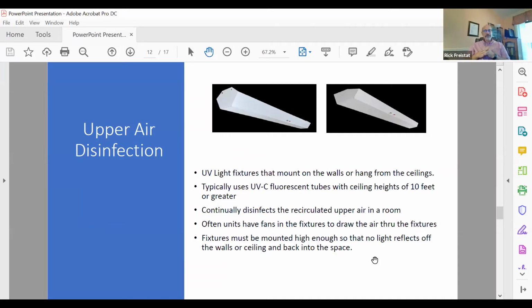The good news about UVC is it disables viruses; the bad news is you can't take too much of it. It's a very strong energy and irradiation that can hurt your eyes or skin. So whenever UVC is being used to kill viruses, you can't be in the room, and fixtures need to be mounted high to ensure light doesn't come down into the room. They're made with baffles so the light throws out almost horizontally and up toward the ceiling, but not back down into the room.